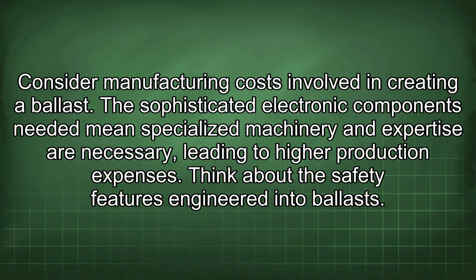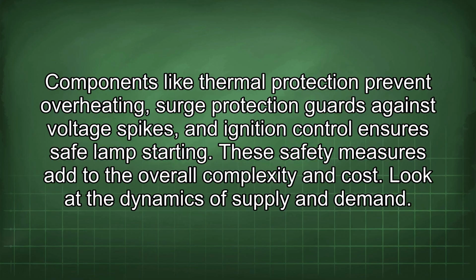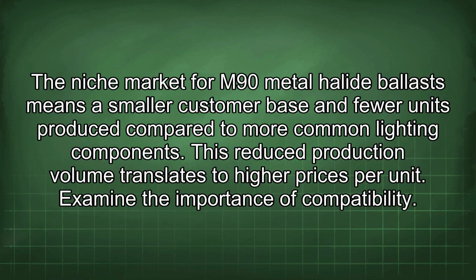Consider manufacturing costs involved in creating a ballast. The sophisticated electronic components needed mean specialized machinery and expertise are necessary, leading to higher production expenses. Think about the safety features engineered into ballasts. Components like thermal protection prevent overheating, surge protection guards against voltage spikes, and ignition control ensures safe lamp starting. These safety measures add to the overall complexity and cost. Look at the dynamics of supply and demand. The niche market for M90 Metal Halide ballast means a smaller customer base and fewer units produced compared to more common lighting components. This reduced production volume translates to higher prices per unit.